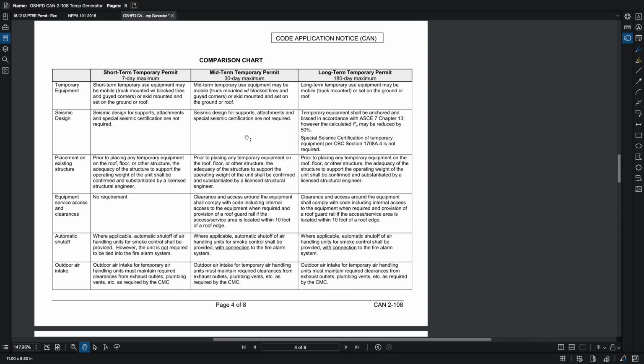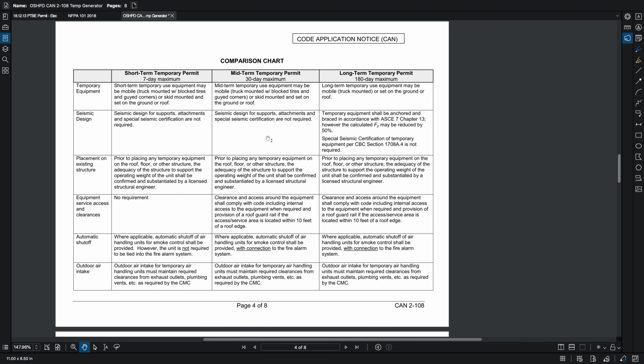One thing that's not called out here, and I'll just touch on, is that a generator requires, under NFPA 110 level 1, a remote monitoring panel. That's not explicitly called out here, but certainly in a short-term setup, because you either have to hardwire it or have a fire watch or an interim fire/life safety measure to monitor the generator.